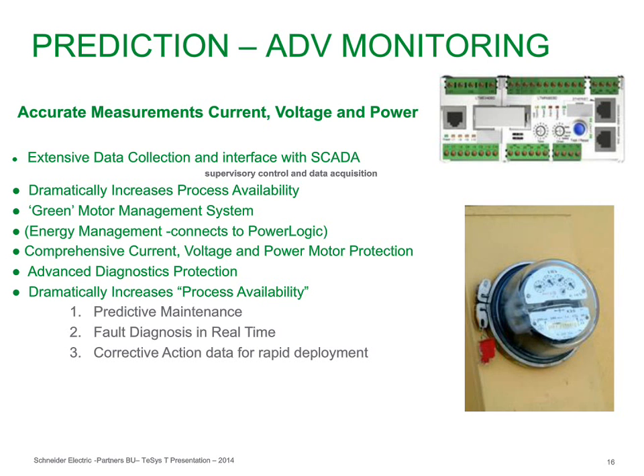And this is one of the big advantages of TeSys T. We measure current, we measure voltage, we measure power, but we can actually collect data over time to do trending on current, trending on voltage, trending on power as well, throughout the day or throughout the operation of a cycle. How we can use this trending, TeSys T has one big advantage: we can do alarms and faults at different settings. So we can separate alarms from faults.